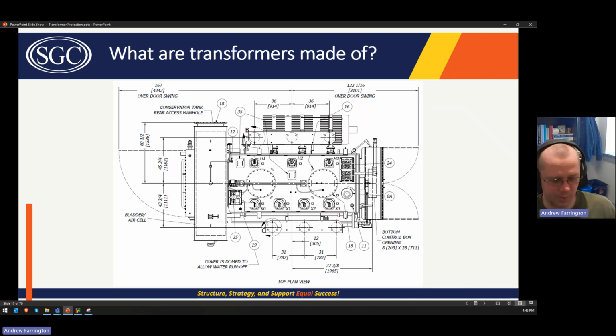So a common issue is when a drafter is drafting a drawing, say with two parallel transformers, and they want to copy one over to another spot, instead of copying it and rotating it and moving it over, they might choose to mirror that transformer. And this happens with breakers a lot too.